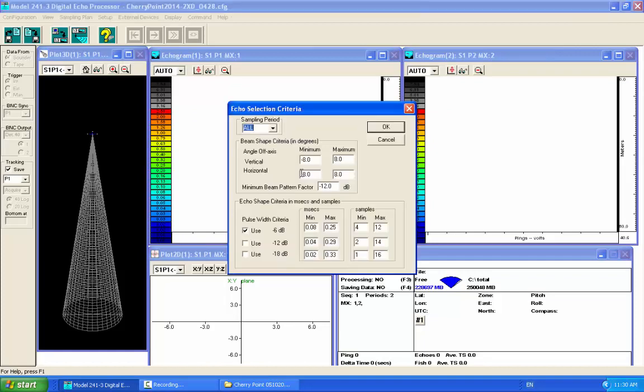The echo acceptance angles, and I remember going through this with Scott way back when over the phone, you do need to remember, basically this is the degree, the measure in degrees, left and right of your beam axis and bow and stern, which really defines a square rather than a circular area that you're accepting echoes from. So this would establish your sampling volume. Again, that also goes back to your transducer. You can't make a 6 degree into a 30 degree. The directivity just isn't there, the sensitivity's not there off axis, but there is some flexibility within the beam patterns to open them up or close them down.